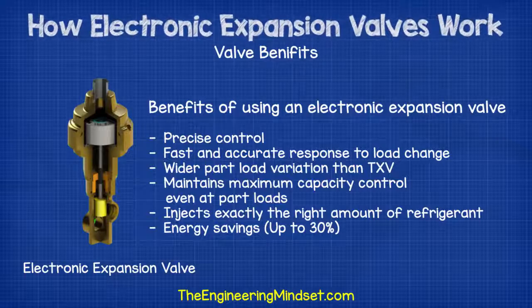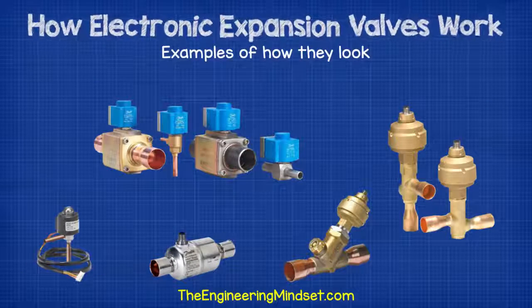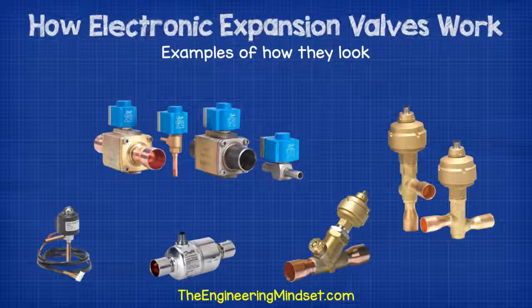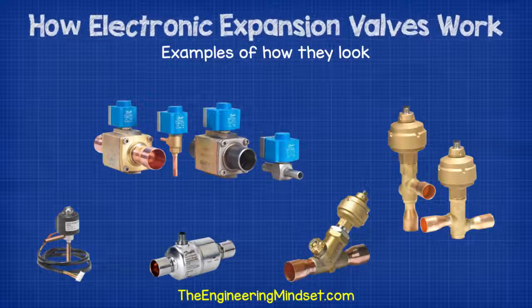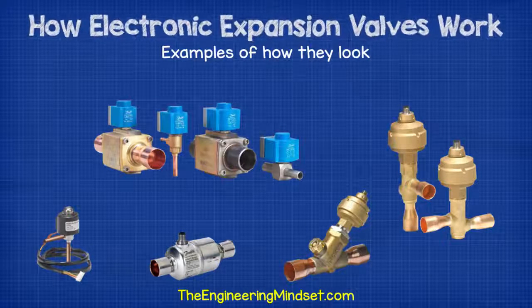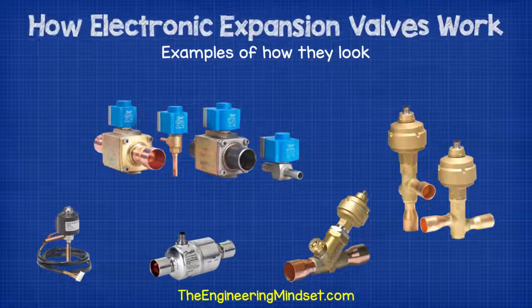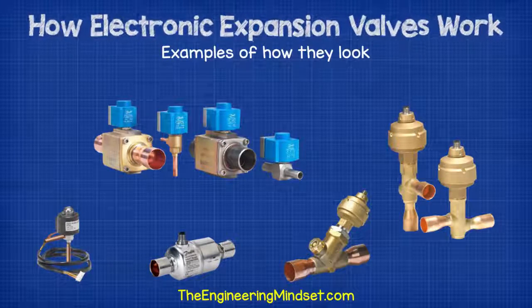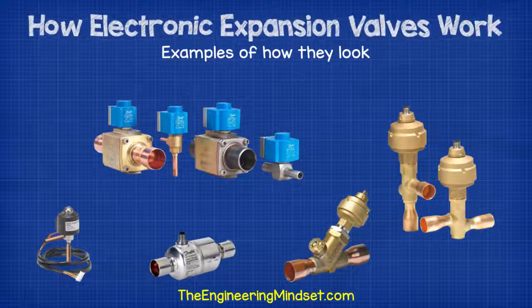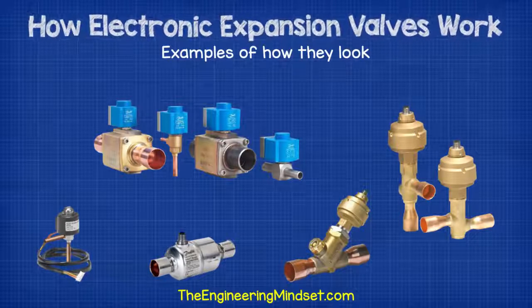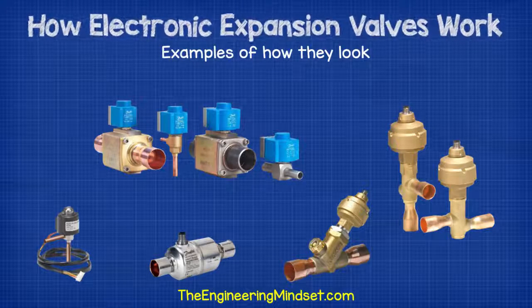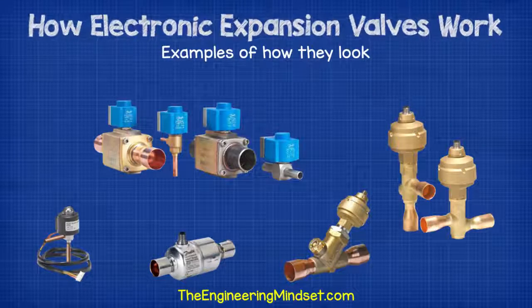What do electronic expansion valves look like? There are many different designs for an electronic expansion valve, and I've put a few examples on screen now so you can see how their appearance varies. The difference in design depends on the type of system, the refrigerant used, and the pressure it's working with. As you can imagine, a small split AC unit isn't going to need the same valve as a high pressure industrial application, so the design is going to vary. Although, the basic working principle is essentially the same.